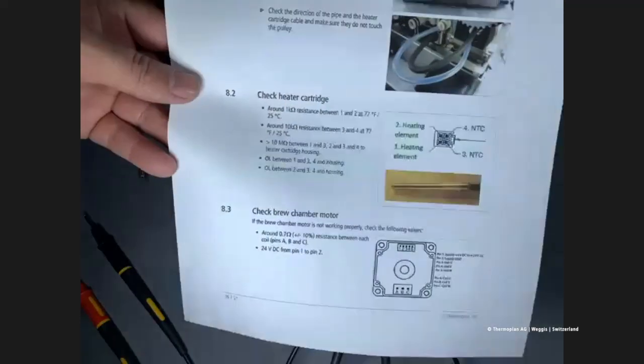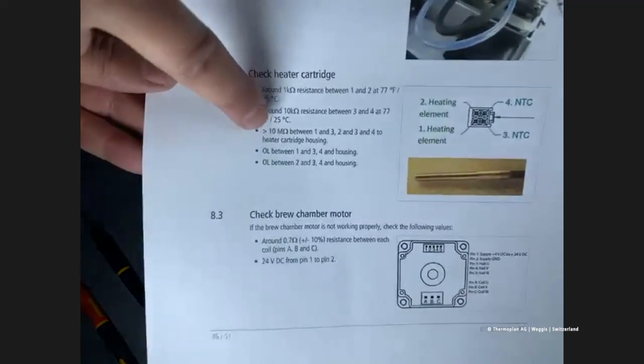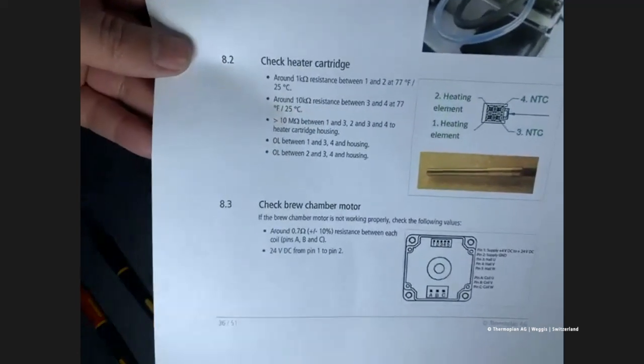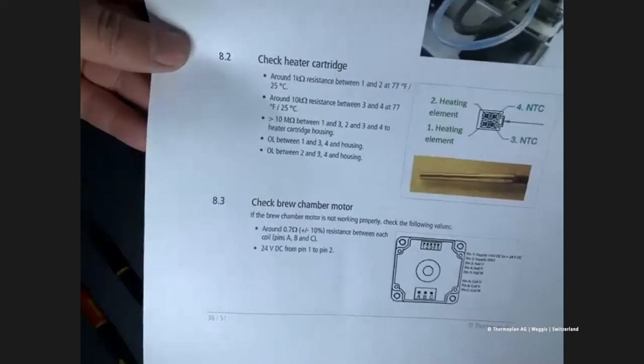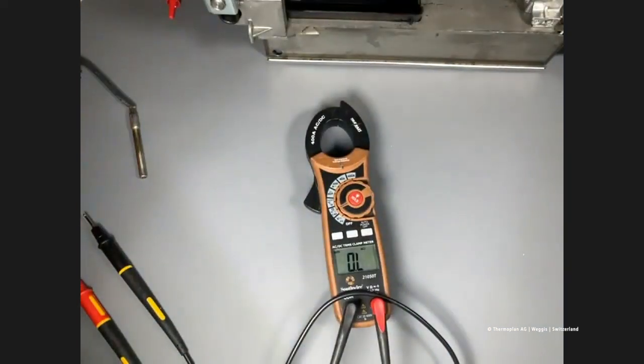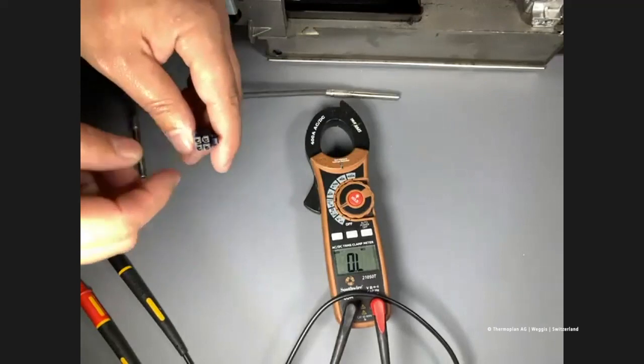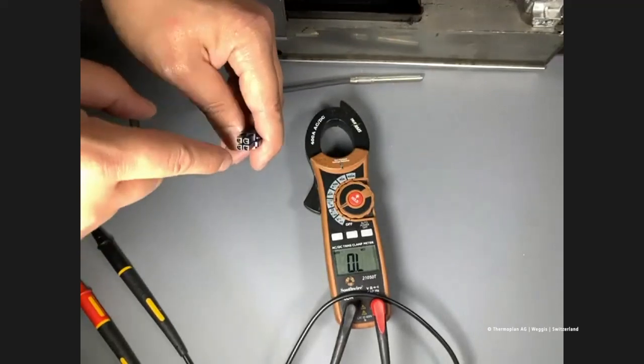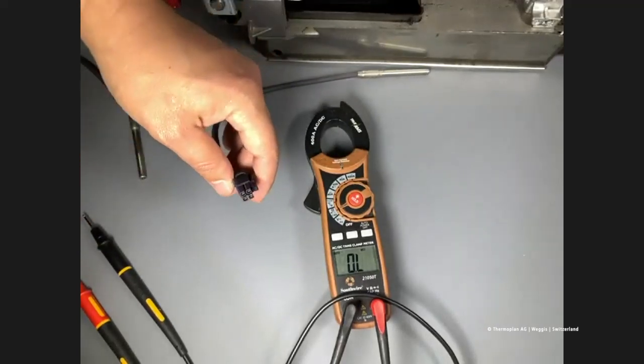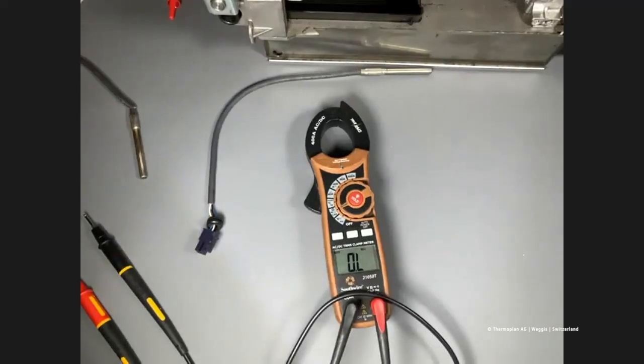And then last, we want to look to see if we have greater than 10 mega ohms between pins 1 and 3, 2 and 3, and 4 to the housing. What we're looking for is to make sure we don't have continuity between the low voltage side and the high voltage side. If those short out, that can typically damage the PCB.